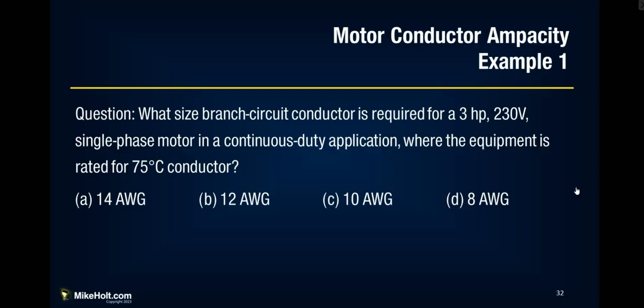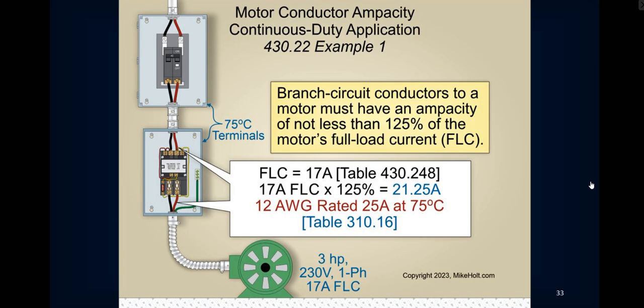So, real quick question here. What size branch circuit conductor is required for a 3 horsepower, 230-volt single-phase motor in a continuous duty application where the equipment is rated for 75 degrees Celsius conductors? First of all, from a test standpoint, oftentimes you're going to see that temperature rating given. What that's doing is taking you to the column you need to be in when you get to 310.16. So, let's just see what they say here.